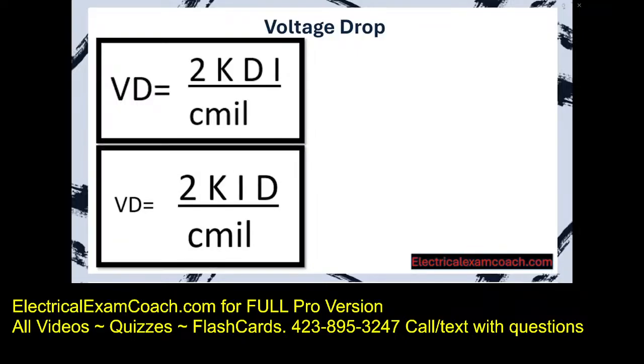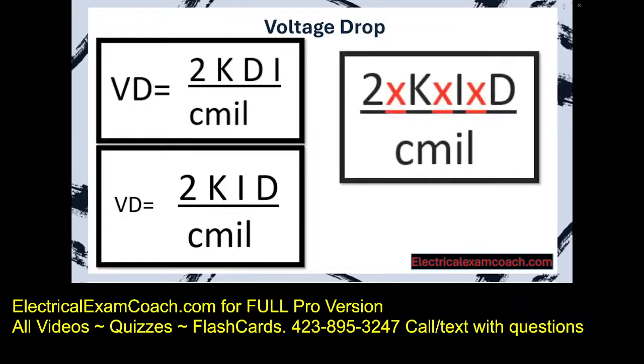I do it like this: 2 K I D over C mil. Easy to remember and easy to plug in. And just like previously in the program, this is implied multiplication. So it's going to be 2 multiplied by K, multiplied by I, multiplied by D, divided by C mils.